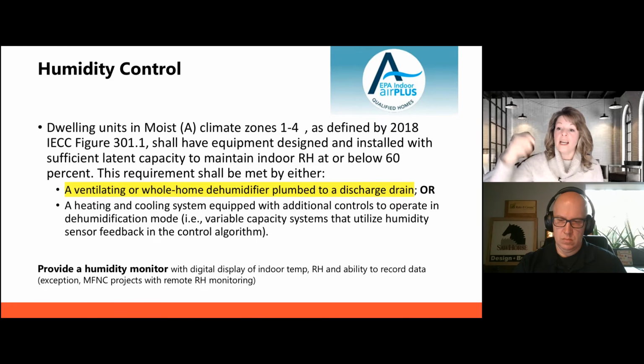And then also, it used to say just a dehumidifier or heating and cooling system, and now they're getting more specific: ventilating or whole-home dehumidifiers, or the heating and cooling system equipped with additional controls to operate in dehumidification mode. Again, we've got to be careful about that dehumidification mode because that is overcooling to dehumidify. So it might not be able to get to that set RH that you want in the home without creating comfort issues by overcooling.